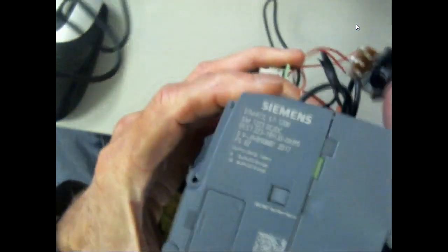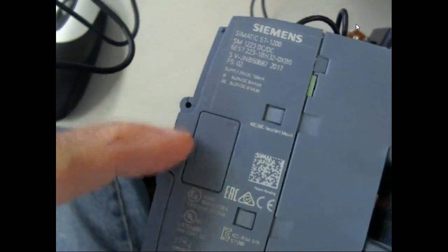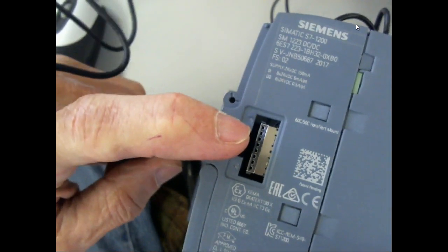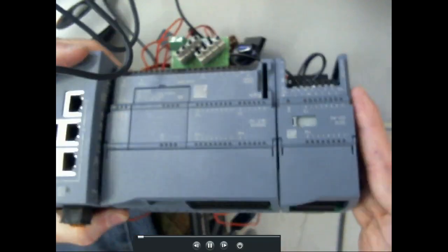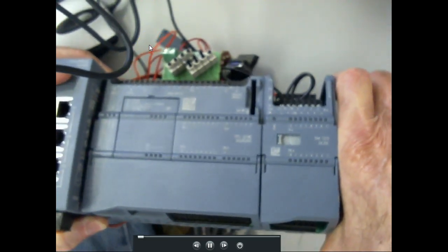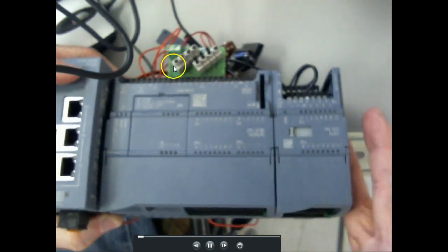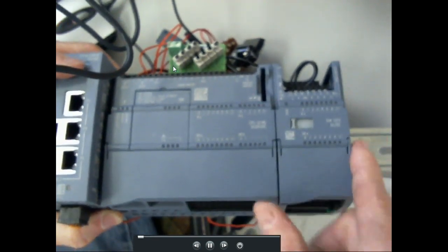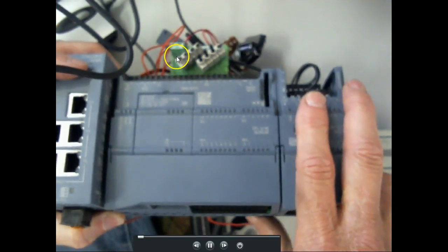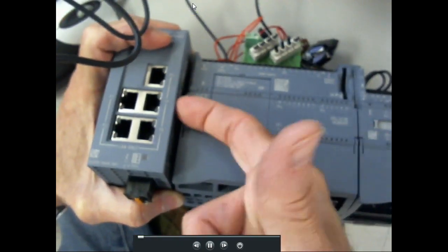Now what they're starting to do is, instead of using a true backplane, they run the backplane through the modules. So if I was to take this off, you would see there's a little snap in here. And if I snap this off, here's the backplane right here. So what I would do is I could buy another module like we've done here, and I could slide it on there and lock it in. And then I can add whatever I want to. I think this guy takes up to, I think it's 8 cards. But they can be input, they can be output. This side is for communication. This side is for input output.